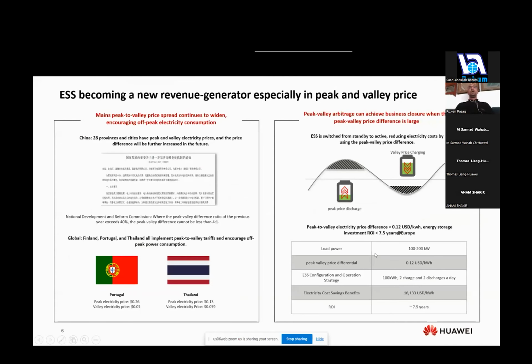Okay, perfect. So on the right-hand side is a typical scenario, as I explained in a couple of slides previously, when you have peak prices occurring at certain times of the day. And this energy storage solution can then provide an offset between the peak and off-peak rates. And the typical ROIs, as seen on the right-hand side, are around 7.5 years.